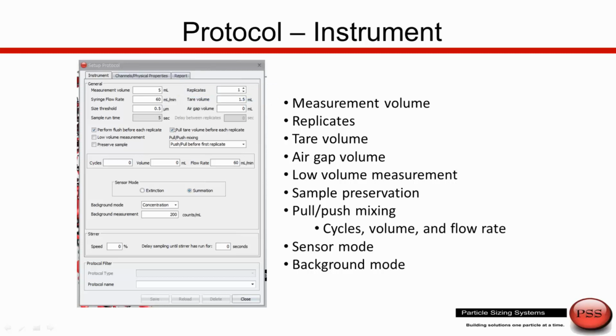Down here we also have the option of how we could do mixing of the sample prior to measurement. We can do this push-pull, where we pull the sample up and down in order to mix a sample, or we could also have an option with a newer system of using mechanical stirring. What kind of concentration limits are we worried about? So this is the way that we control the measurement for a given sample, and we could use this protocol for a given tube or for all of the tubes in the sample tray. So these are some of the options that we need to program in to make sure that we've optimized the measurement for the kind of sample and the data reporting required for the measurement that we're about to make.